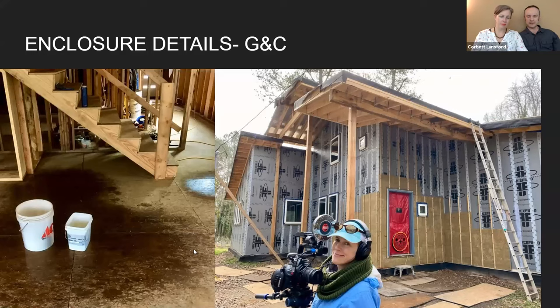For Corbett and Grace, like Bill used a passive house tool for energy modeling, they used an energy model called REM, which is what HERS raters use. They energy-modeled the house so all the decisions — how much exterior insulation, how much cavity insulation, how much air tightness — were informed. They also did a load calculation. To be clear: those two are mutually exclusive — an energy model is not a load calculation. You need to do an actual Manual J, and Manual J software is not good at doing energy modeling normally.